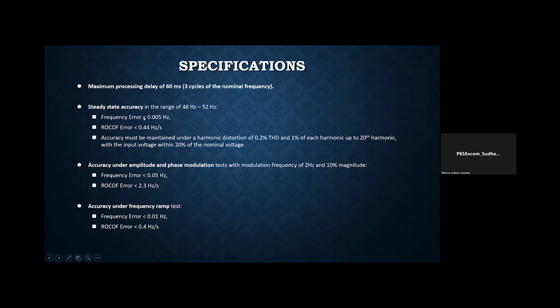For example, frequency error should be less than 0.005 hertz - you can see how critical these things are. And the rate of change of frequency error should be less than 0.4 hertz per second. This should be valid for all frequencies ranging from 48 hertz to 52 hertz. The accuracy must also be maintained in the presence of harmonic distortion of 0.2%, and 1% of each harmonic up to the 20th harmonic, with the input voltage within 20% of the nominal voltage - that would be the measuring voltage.